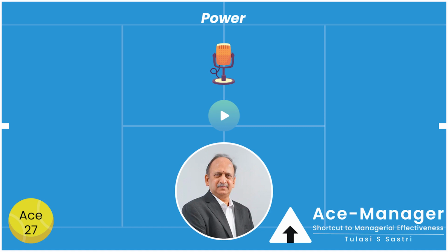In the case of power purchased from the electricity boards, we need to note that broadly there are two types of charges. One is called demand charges, based on the highest quantum of power drawn at any given point of time in a period. The second is called consumption charge, representing the actual units consumed in a period.